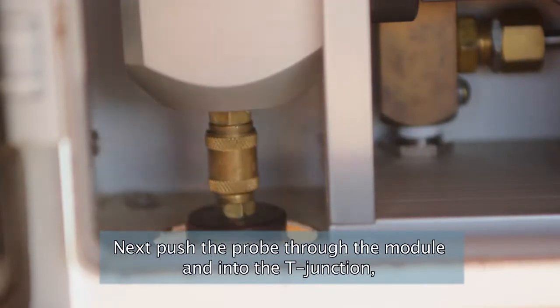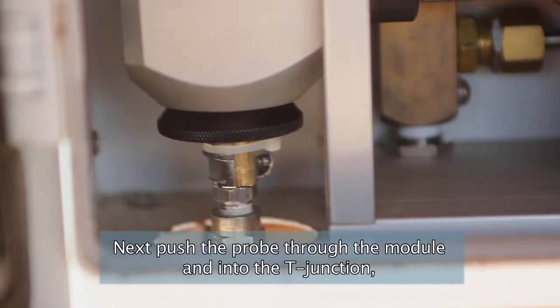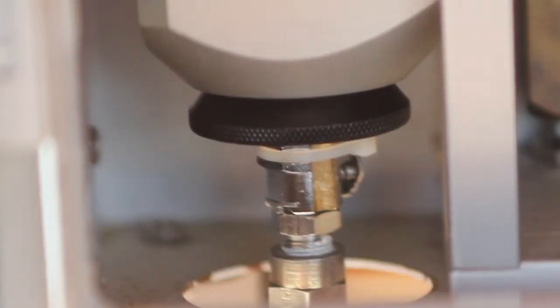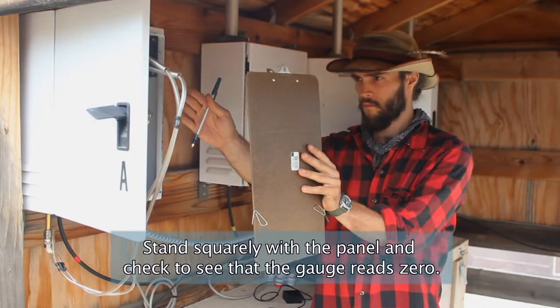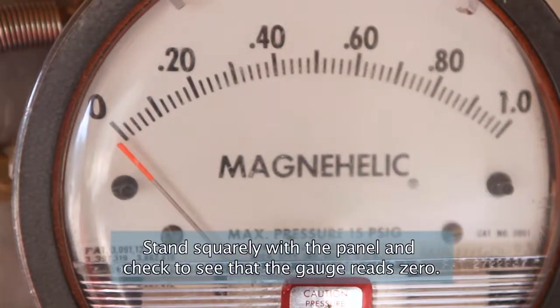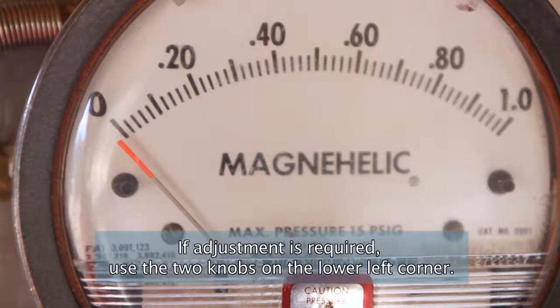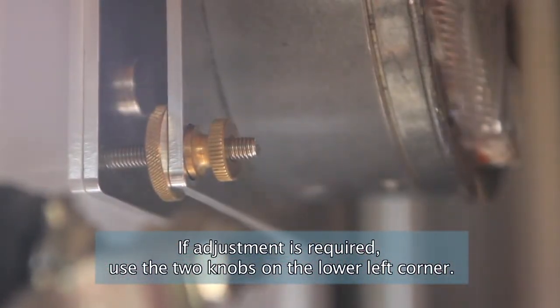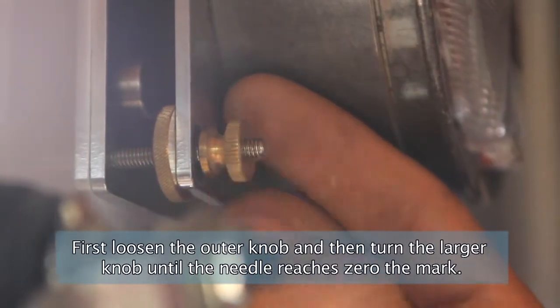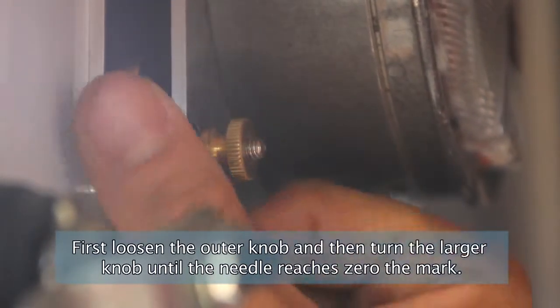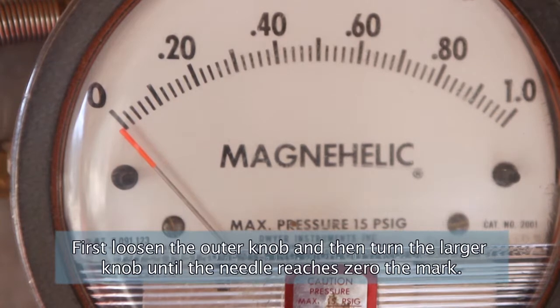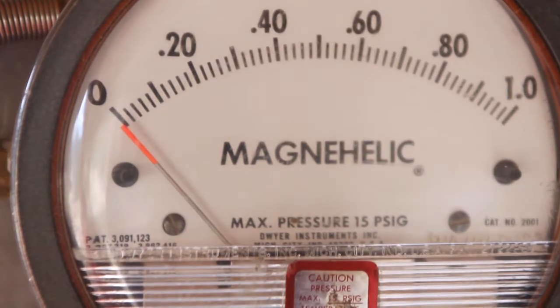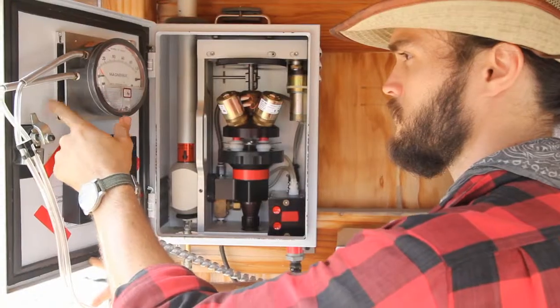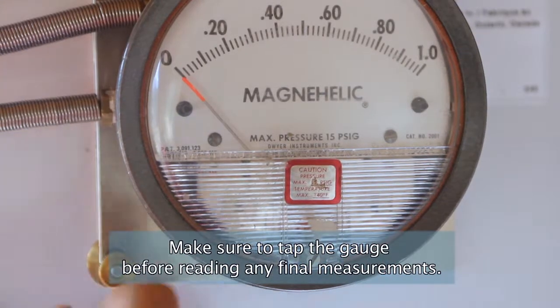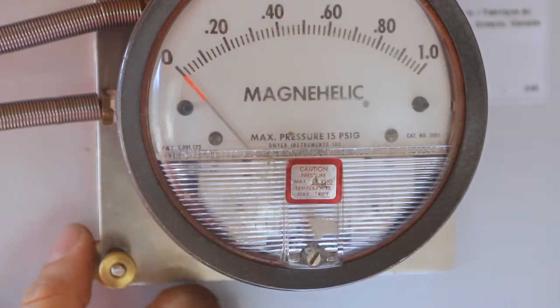Next, push the probe through the module and into the T-junction, bottoming out the probe. Stand squarely with the panel and check to see that the gauge reads 0. If adjustment is required, use the two knobs on the lower left corner. First loosen the outer knob, and then turn the larger knob until the needle reaches the 0 mark. Make sure to tap the gauge before reading any final measurements.